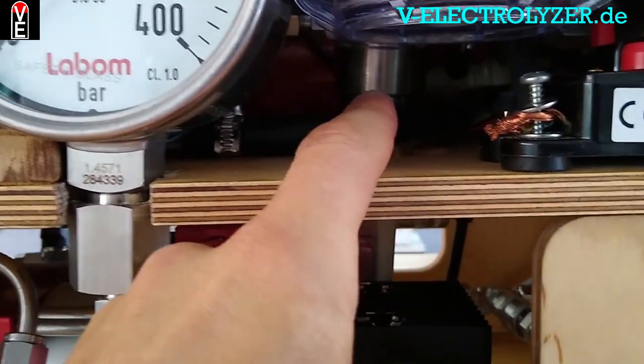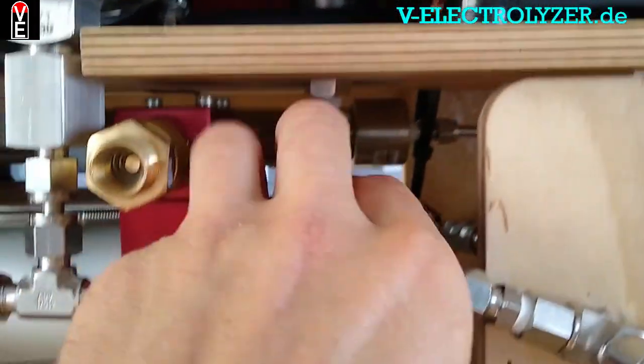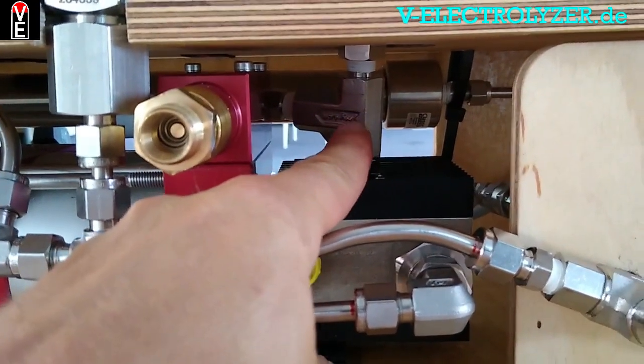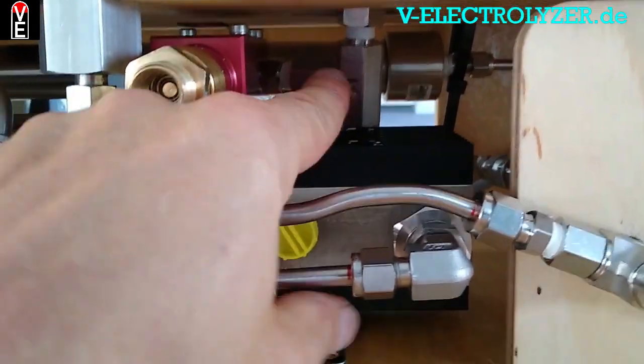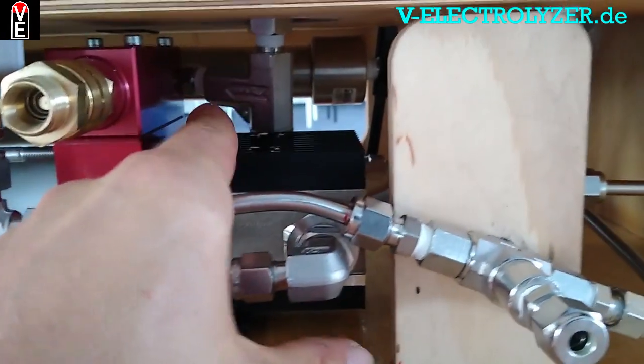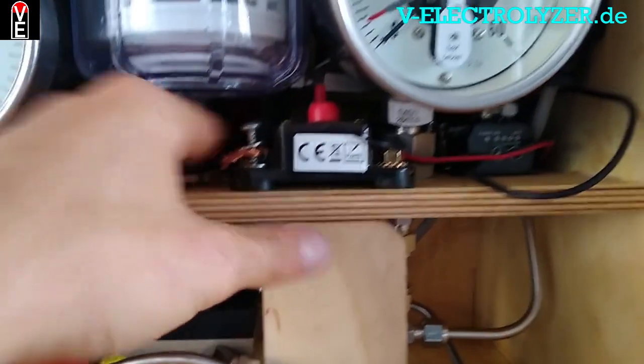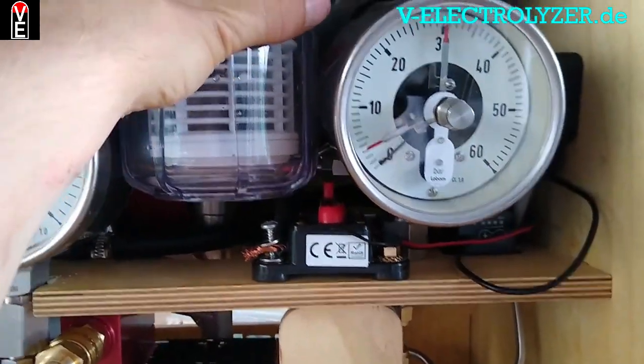The coalescence dryer — water is dripping out here below. This dryer has a relief valve: when the relief valve opens, the water will automatically go out and go back into the water system. There is also a valve here — if you unscrew the deionizer you will get to it.